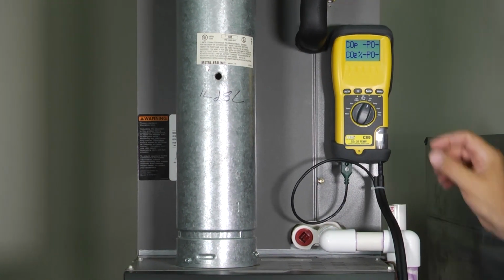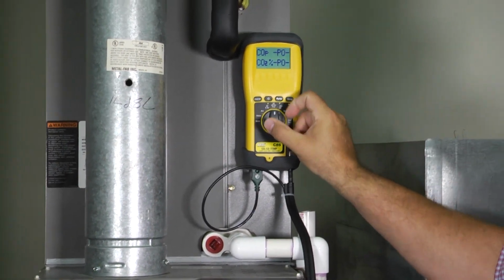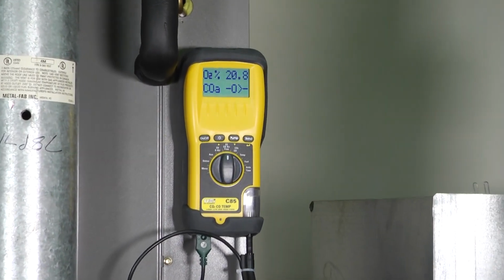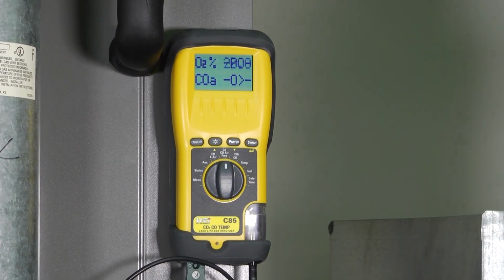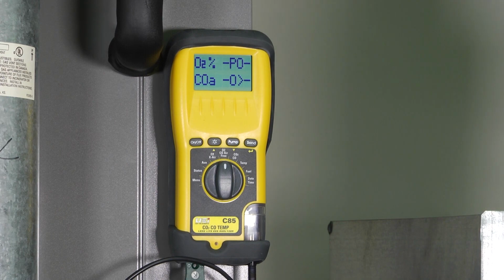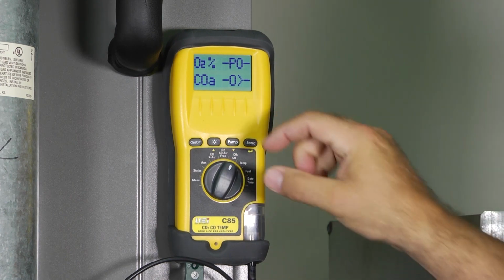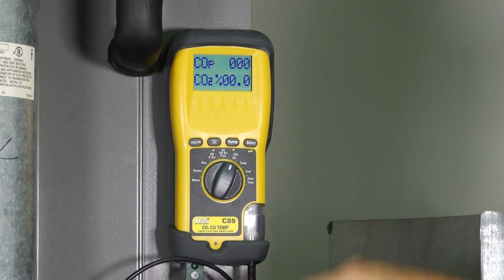So really when it comes to my analyzer, the first thing I'm going to want to do is turn my analyzer on and let it come up and clear itself out, and I always want to do that in free air. Now, because of what we're doing today, I've already done that in our system, and I've taken it and cleared it and it's been in free air.